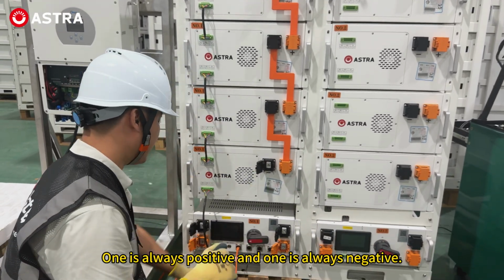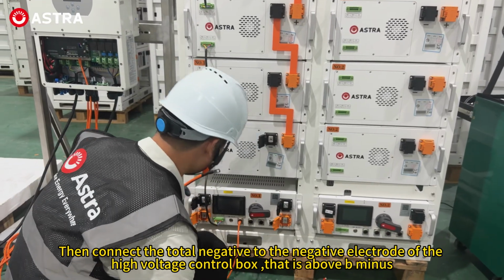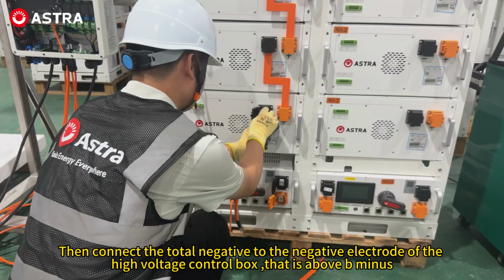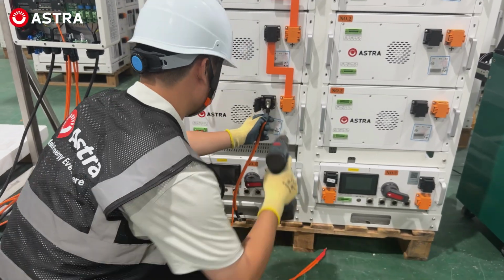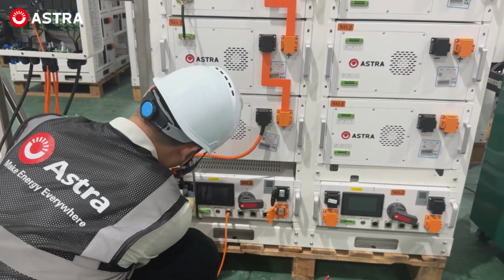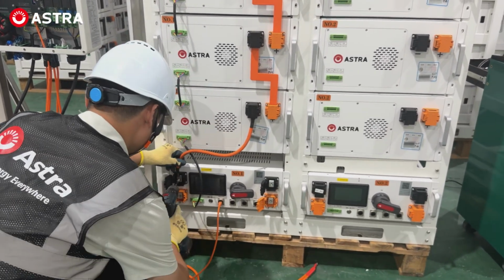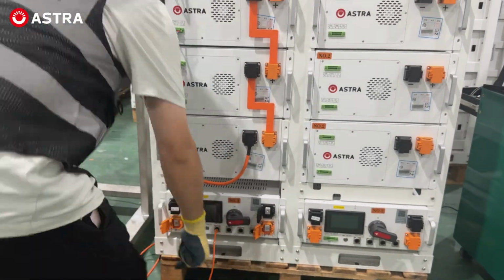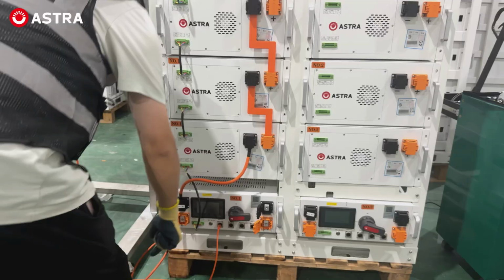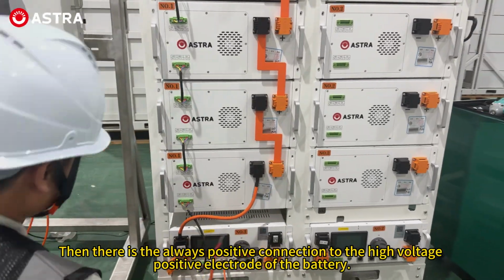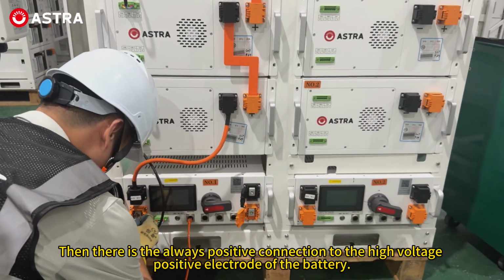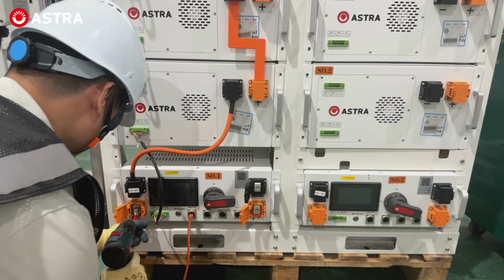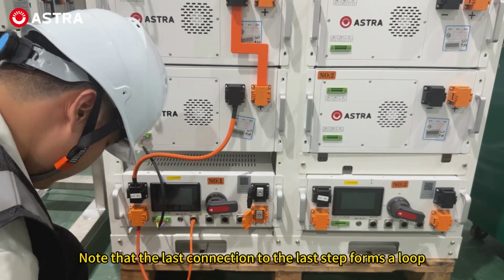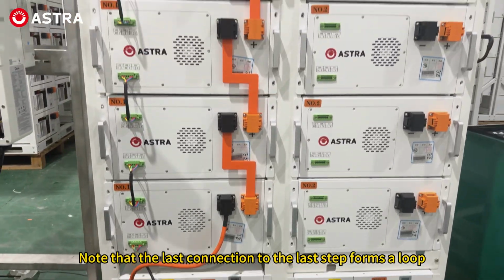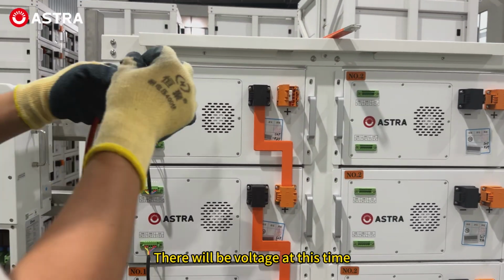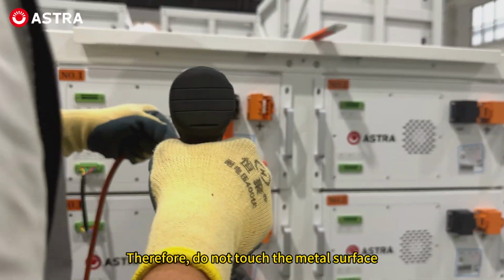One is always positive, and one is always negative. Then connect the total negative to the negative electrode of the high voltage control box, which is marked B-. Then there is the always positive connection to the high voltage positive electrode of the battery. Note that the last step forms a loop. There will be voltage at this time. Therefore, do not touch the metal surface.